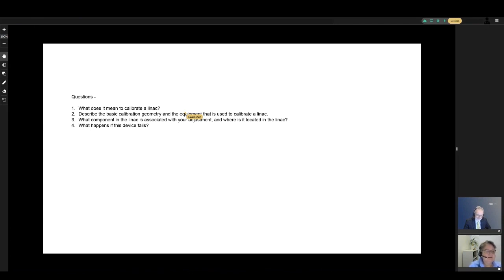The other thing it does, it tracks flatness and symmetry. So that won't happen then. And I think if it fails, you get all kinds of interlocks. Okay, so you've determined that this device has failed, and you need to do something in order to get the Linac back to being in operational state. So you replace this device, the monitor chamber. Tell me a little bit about the QA that you would do to make sure that you can then turn the Linac back to the therapist for patient treatment.